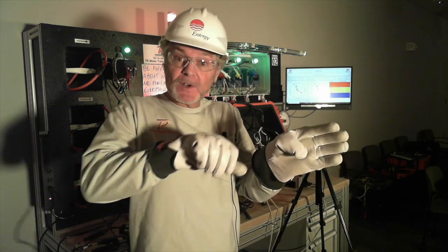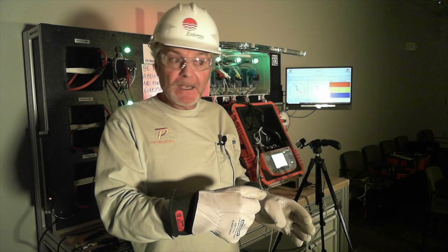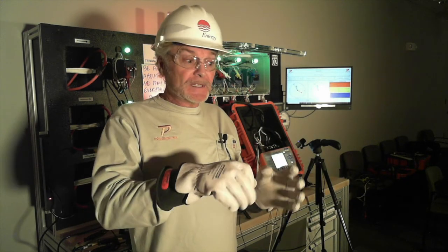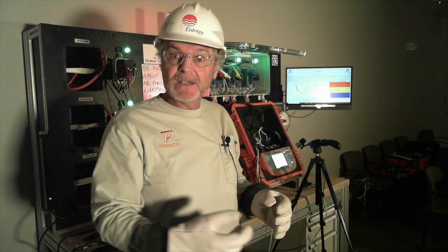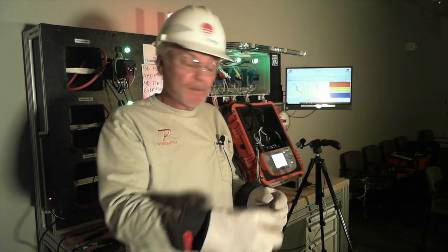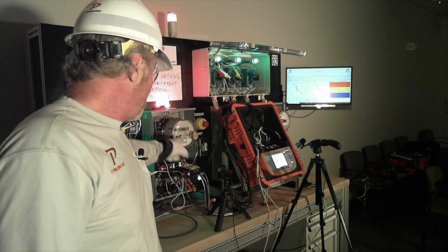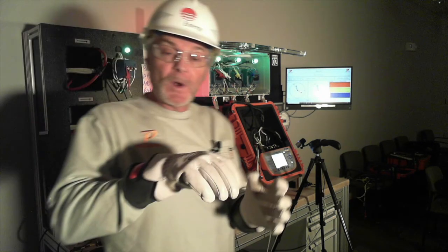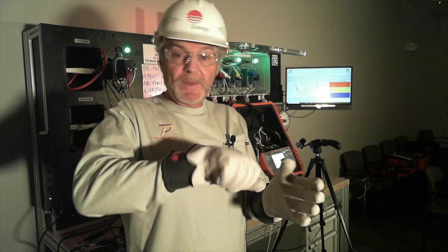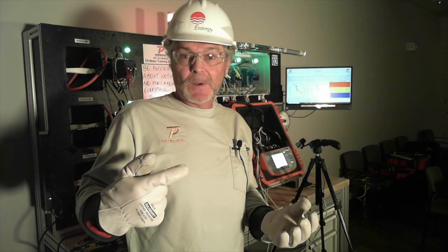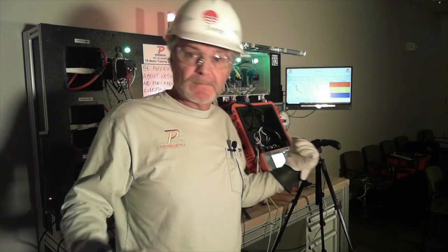So now I can start tightening things up on A phase. I've had guys call me up, rolling down the road, and they say, hey, I did what you said, and I got in there with my nut driver, and I started tightening, and sure enough, I found a loose one, tightened it up. There's a lot of connections in there. Think about all those connections. And if one of those is loose, then the burden goes up because the resistance goes up, right? So then when they tighten it down and retest, it went from 1.2 to 0.4.